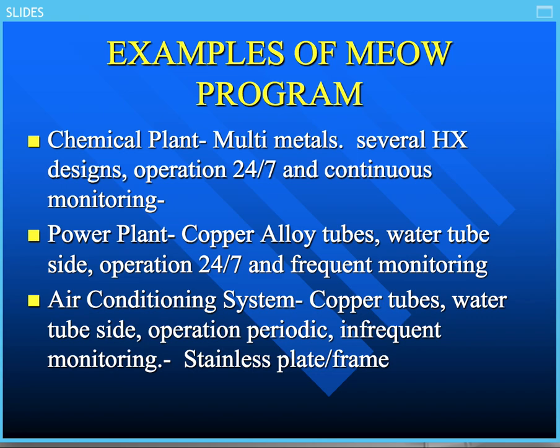Air conditioning is a lot like a power plant, except that it's periodic operation. It's infrequent monitoring, and they can have stainless steel plate and frame heat exchangers tying in with the chill water system. But air conditioning requires a lot more biological control, a lot more scale control, because it is periodic operation. Frequently, your machine shuts down. So consequently, that's the difference in how you use the MEOW program to say, here's the type of treatment program that I could come up with based on knowledge of what's in the system.